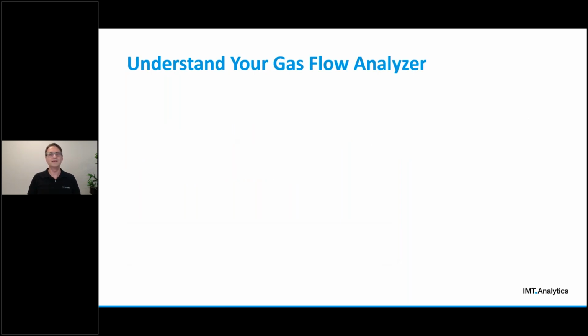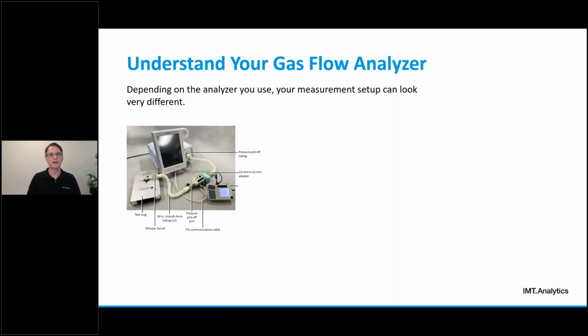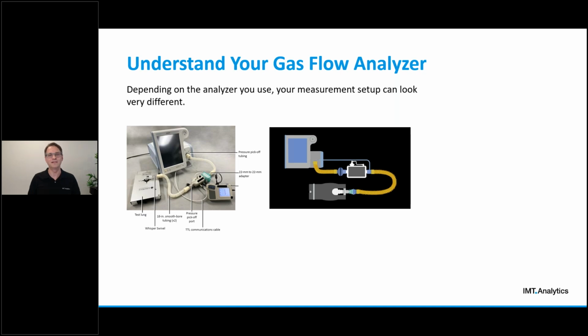So, of course, we can't expect ventilator manufacturers to add setup pictures for each and every gas flow analyzer available on the market. Therefore, it is very important for you to understand the gas flow analyzer that you use in your daily business, because depending on the analyzer you use, your measurement setups can look very different. For example, the setup we've seen in the picture before, here on the left-hand side, can look as simple as in the picture on the right-hand side with a different analyzer. In the example on the right side is our Citrex H5, which is a so-called all-in-one device that measures all the relevant parameters right inside the flow channel, allowing the simplest possible setups.